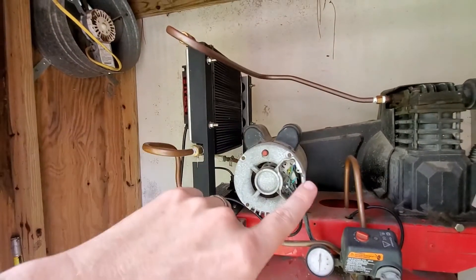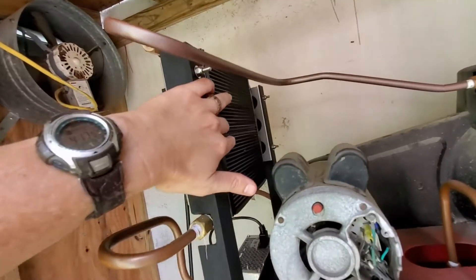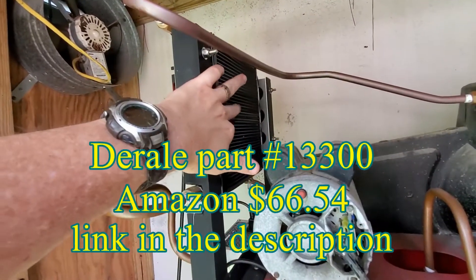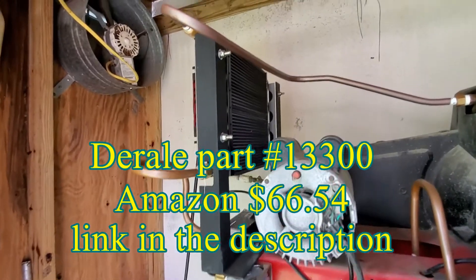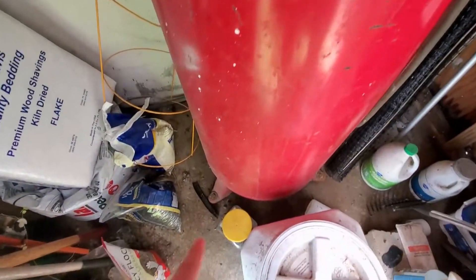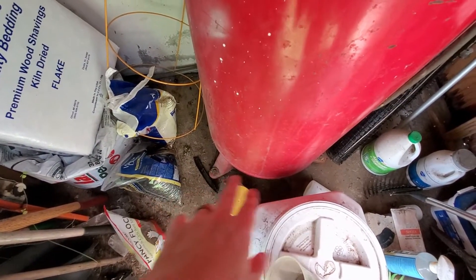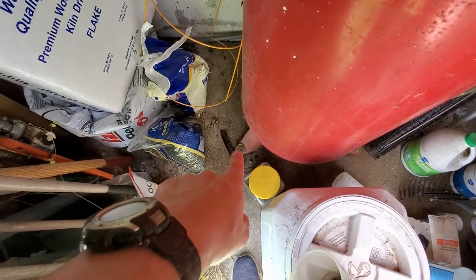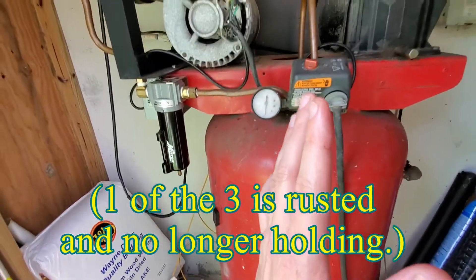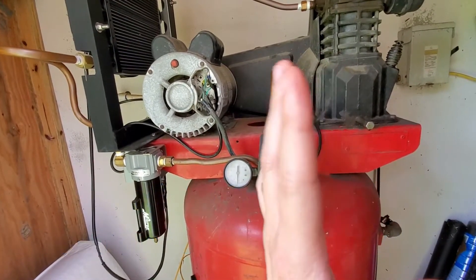That's one thing I need to address, and I think that'll solve it. Good news is I think I can buy just the cooler without the fan, but it's about $60 — so a little bit of a hit. This compressor is not bolted to the floor; it's got some bolts but I think they're all rusted through, which I believe is contributing to extra vibration resonating through the whole system.